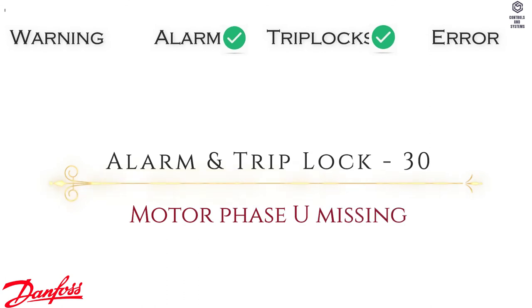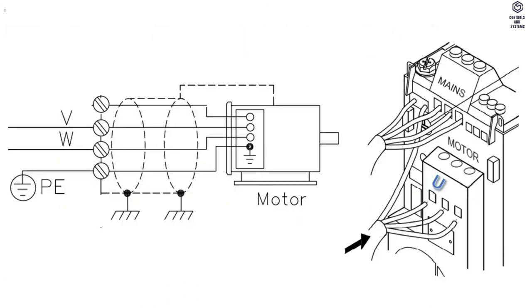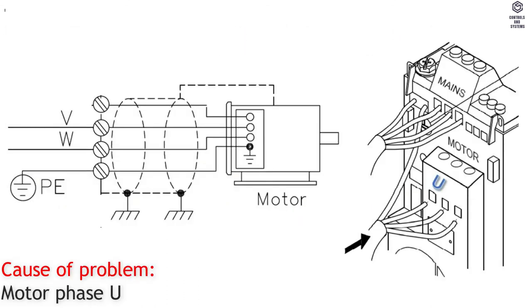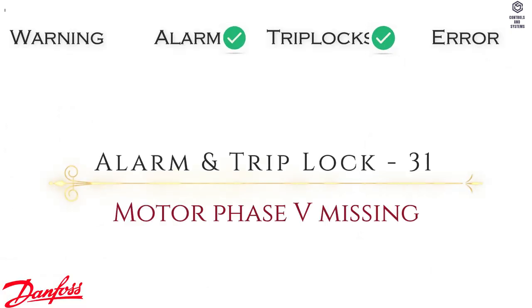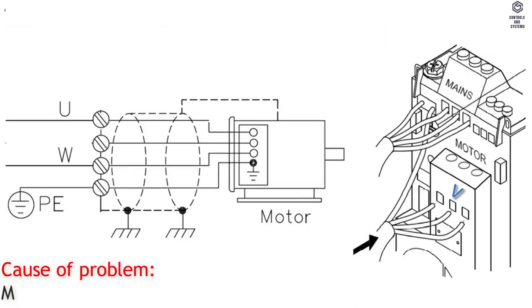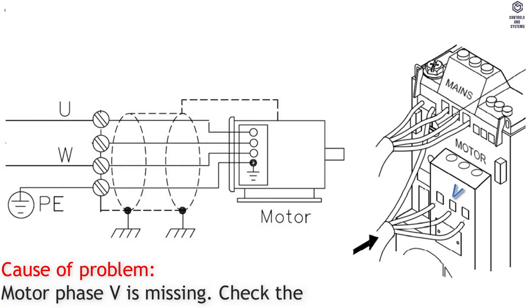Alarm and Trip Lock 30: Motor Phase U Missing. Cause of Problem — motor phase U is missing. Check the phase. Alarm and Trip Lock 31: Motor Phase V Missing. Cause of Problem — motor phase V is missing. Check the phase.